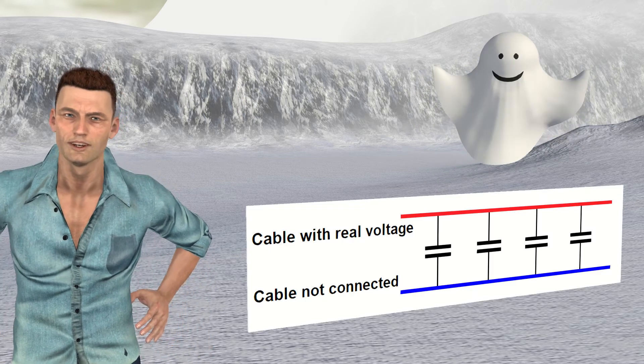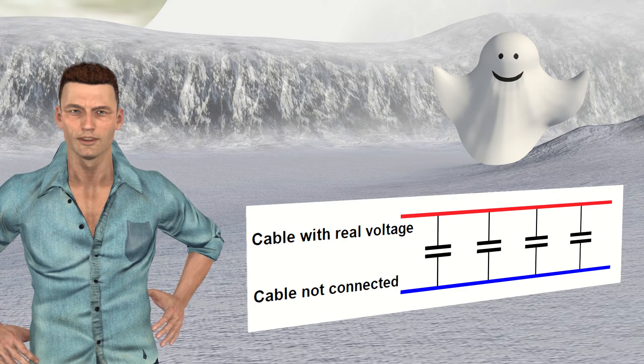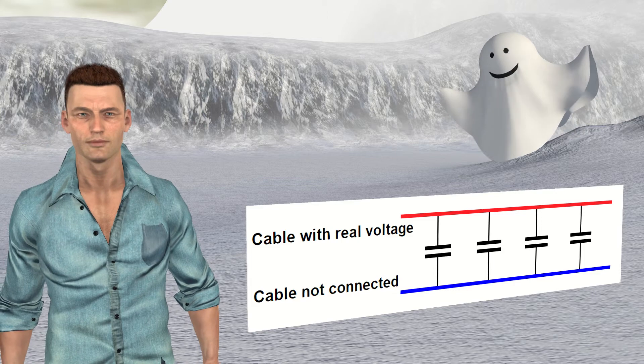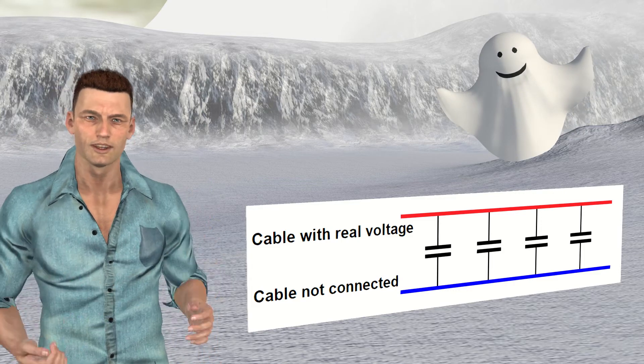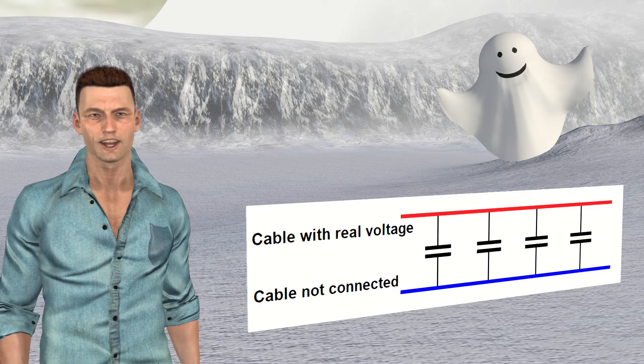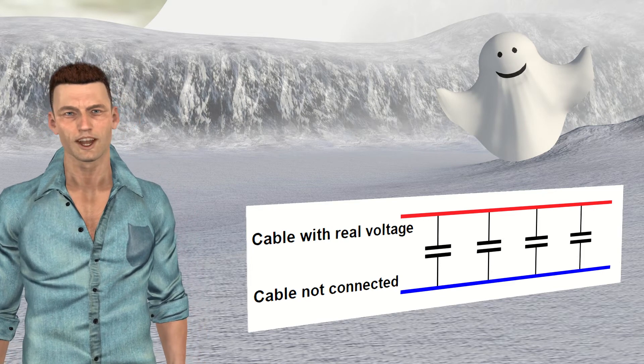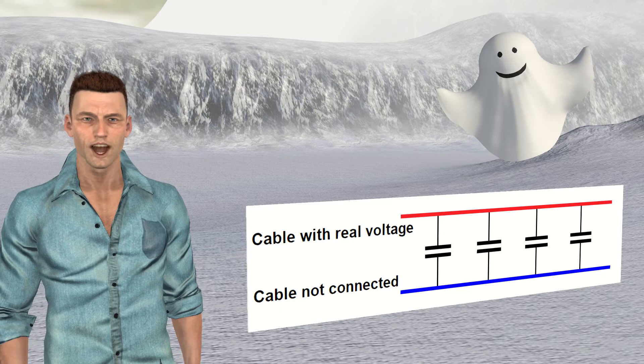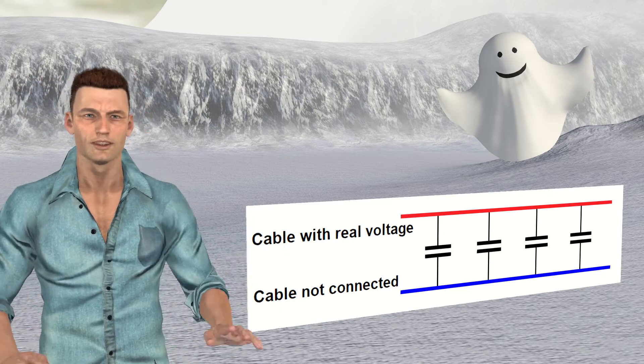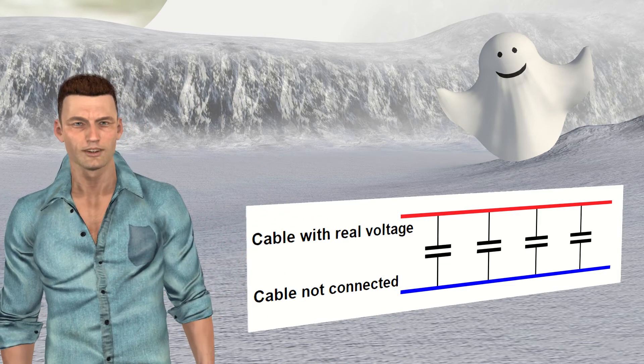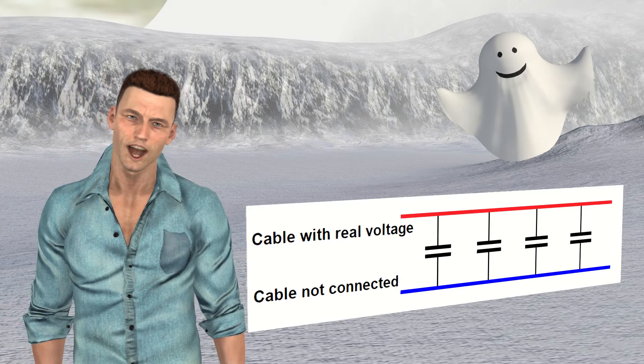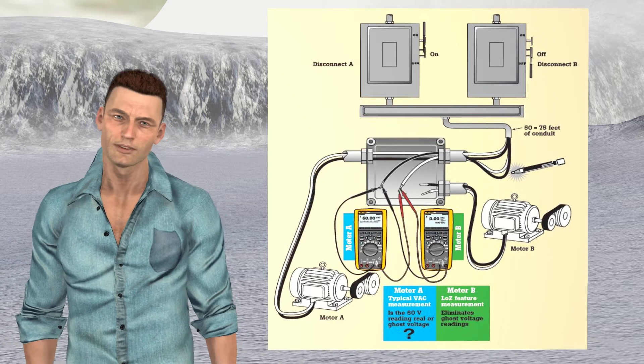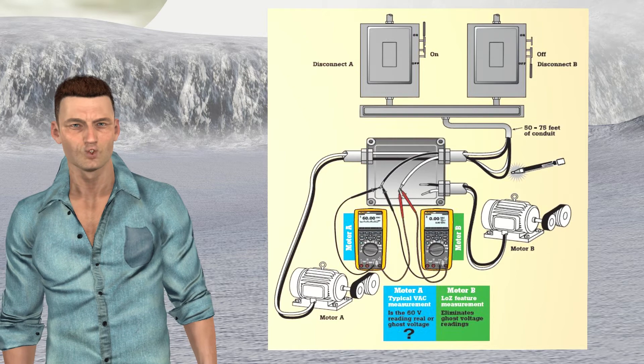Sometimes, when we have cables without voltage running alongside cables that are in operation inside the electrical distribution ducts, this can create a kind of capacitor between the cable without voltage and the cable in operation. We say that a capacitive coupling effect can occur between those cables, which gives rise to the appearance of a voltage in the non-powered cable. This induced voltage is what is known as a ghost voltage. This situation can appear in open fuses or protections, in unused cables installed for future needs, in systems with disconnected grounds, etc.